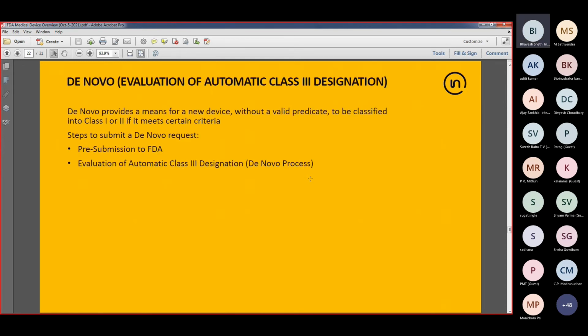The other type of submission that I mentioned earlier is De Novo. What if you end up having a new device, but that doesn't have a valid predicate, or if it doesn't fit any classification? As I mentioned earlier, you can reach out to FDA through the 513(g) inquiry, and FDA may come back and say, well, we don't have any product classification for this device type that you have, and you'll need to do a De Novo for this. Well, De Novo is a regulatory submission as well, and it's specifically for novel devices.